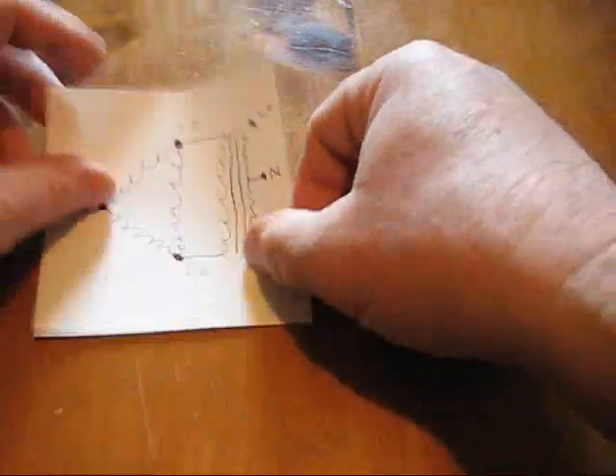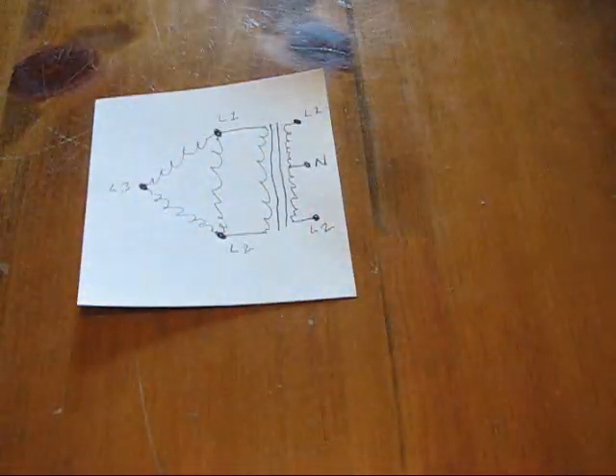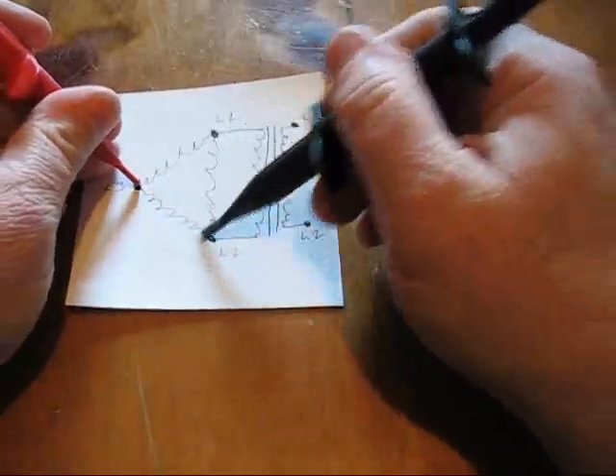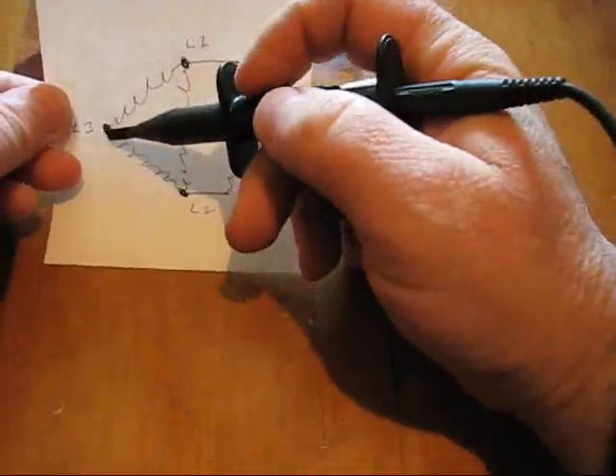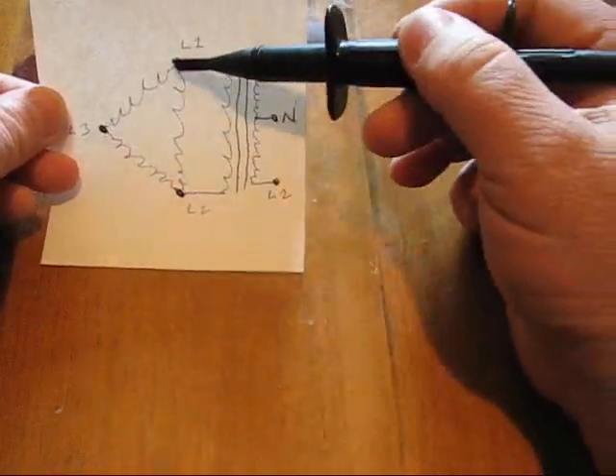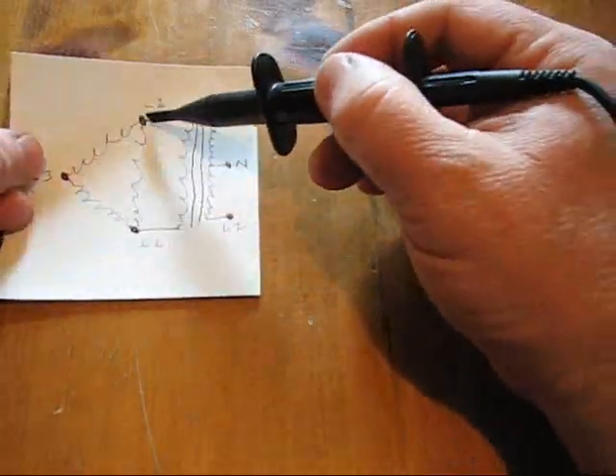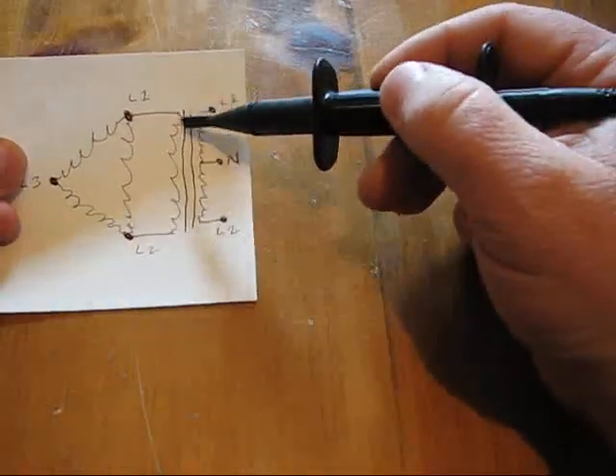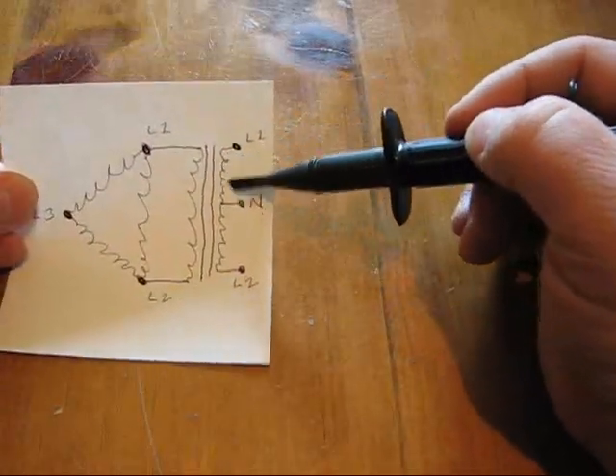If you have to have a neutral connection with that kind of setup, you have to add a transformer. This shows a center tap transformer. This is still just a delta connected set of three windings. In a home, you wouldn't have this third one. It's still there at the generator, but you only get these two. You've got 220 volts across L1 and L2. You can connect that to a transformer with a center tap secondary, and that provides your neutral if you need it.